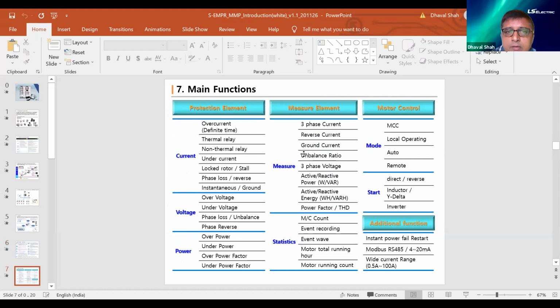So what are the main functions? If we look at the main functions, it is a protection element, a measurement element, and it can control the motor center. When it comes to the protection element, you get overcurrent, definite time or inverse time, thermal relay, non-thermal relay, undercurrent, locked rotor current, phase loss, reverse phase, instantaneous, and ground fault. Moving on to voltage protection: under voltage, phase loss, unbalance, phase reverse, and of course power: over power, under power, over power factor, and under power factor. All these things can be measured: active and reactive power, active and reactive energy, power factor, and as mentioned earlier, 16th harmonic THD of current and voltage.